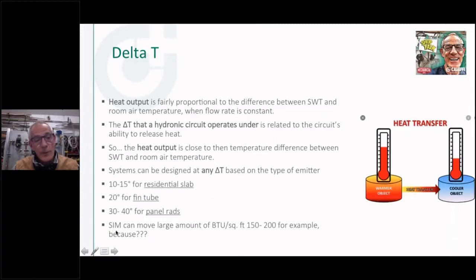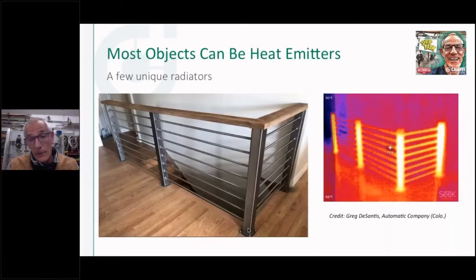And if you think about it, if we do a snow and ice melt, we can move a lot of BTUs per square foot, 150, 200, even more. Why would that be? Why can we move so much more out of a square foot of concrete in a snow melt compared to inside the building? Well, the delta T. If you look outside and it's 30 degrees, the ambient air temperature on that slab is 30 degrees. If I'm supplying it with 100-degree water, I've got a huge delta T to work with, so I can get a lot of BTU output out of a square foot of concrete sitting outside, where that wide delta T is driving that heat transfer.